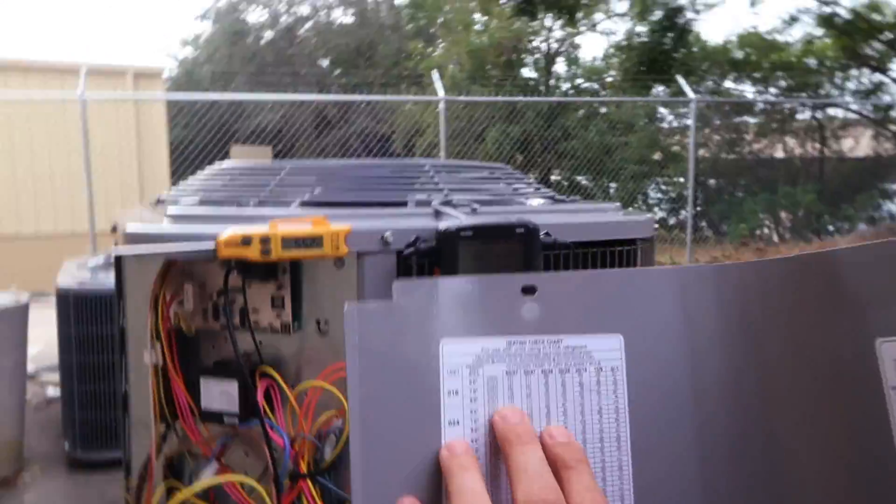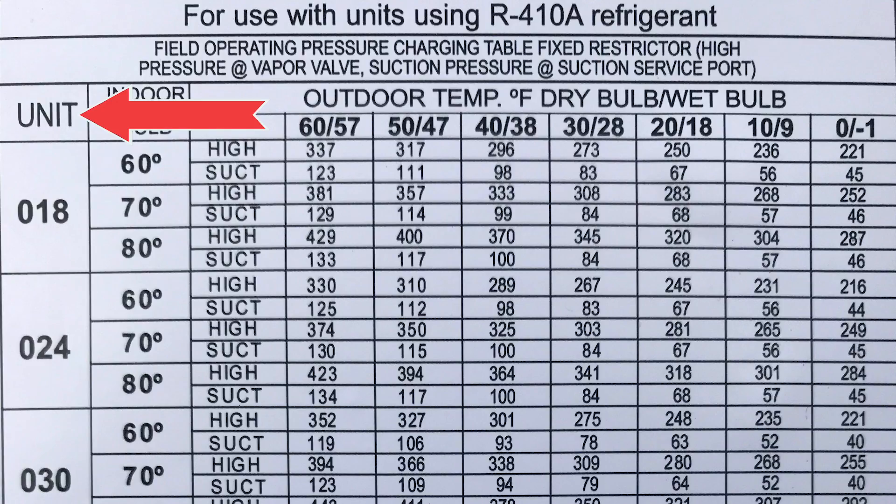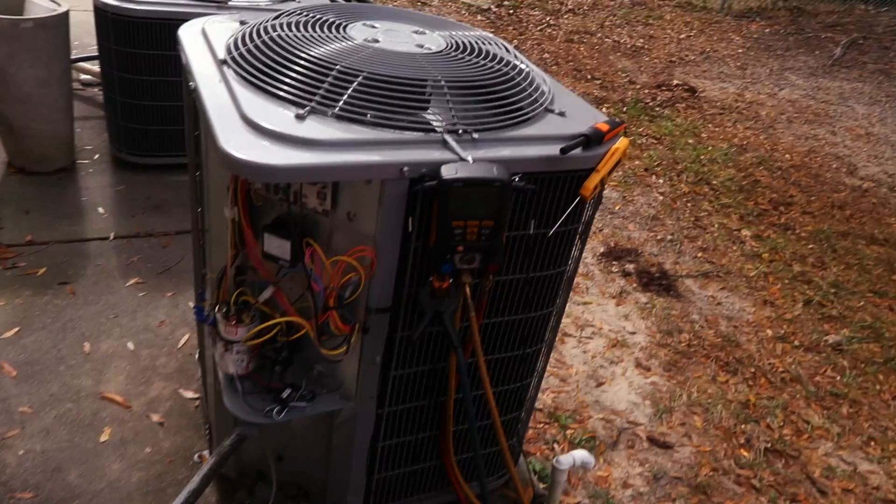Here is our charging chart for heat mode. Our indoor temperature — here you select a unit. This particular one is a two-ton system. Our indoor temperature is 70 degrees, and our outdoor temperature is right about here, about 57, between 60 and 57. So if you scroll down, based on our tonnage and indoor temperature, our suction should be approximately 130 psi and our discharge pressure should be right around 374. We'll give this about five to ten minutes of runtime.